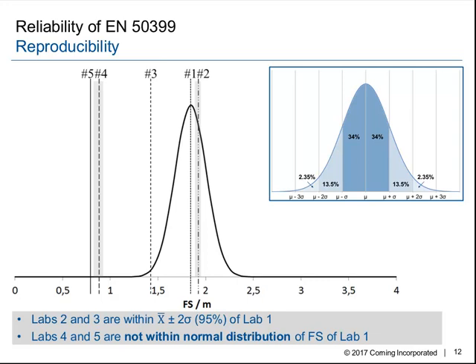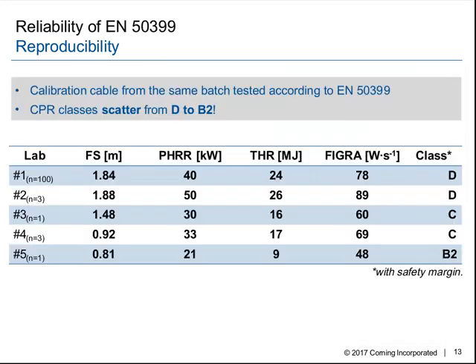If we want to have a more detailed look at the results, and let us focus on the flame spread, we see that laboratory 4 and 5 have only half of the flame spread that was achieved in laboratory 1 and 2. At this point, I of course have to add that in laboratory 1 we had 100 experiments, and in laboratory 2 to 5 only 1 to 3. So there is not such a statistical confidence behind these values. However, during our 100 experiments, we never achieved flame spreads below 1 meter. So this was a very unusual result for us, especially because CPR classes do scatter here from a D up to a B2.